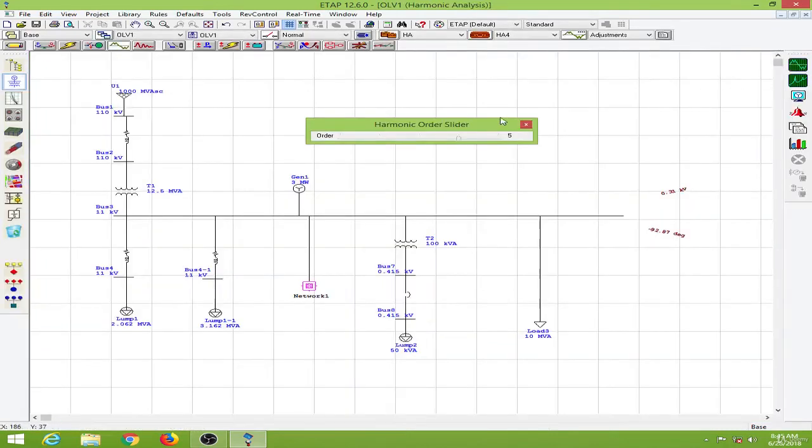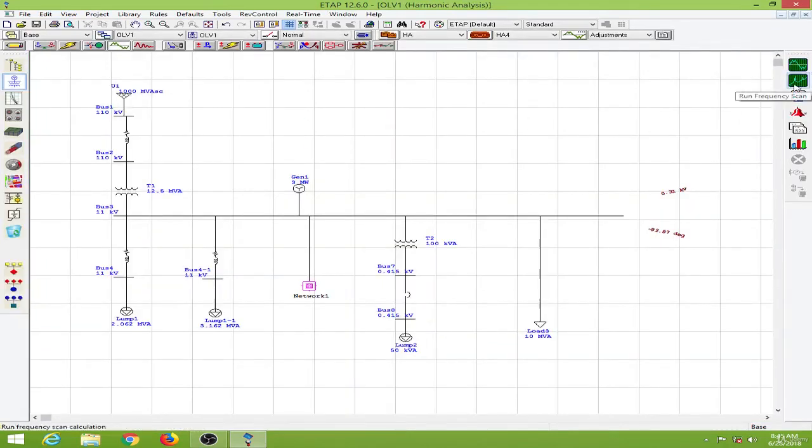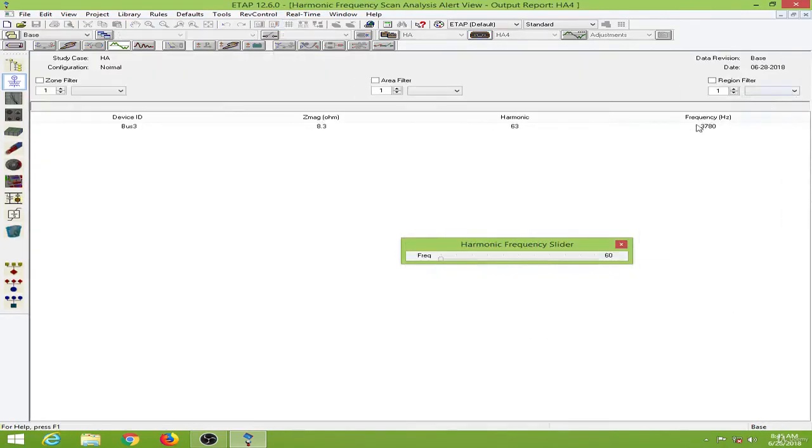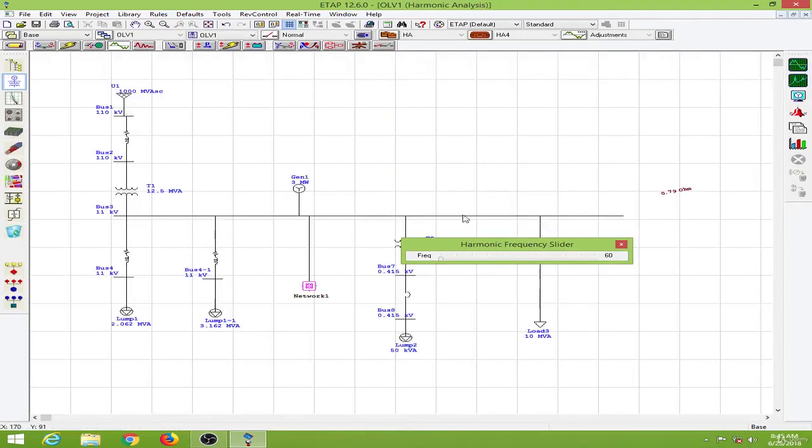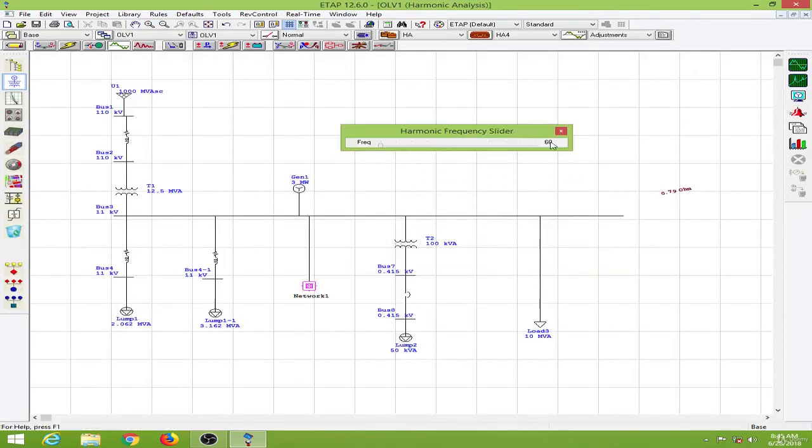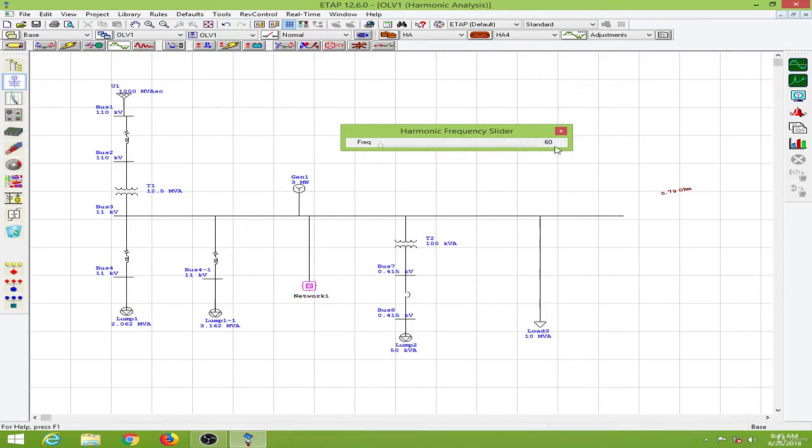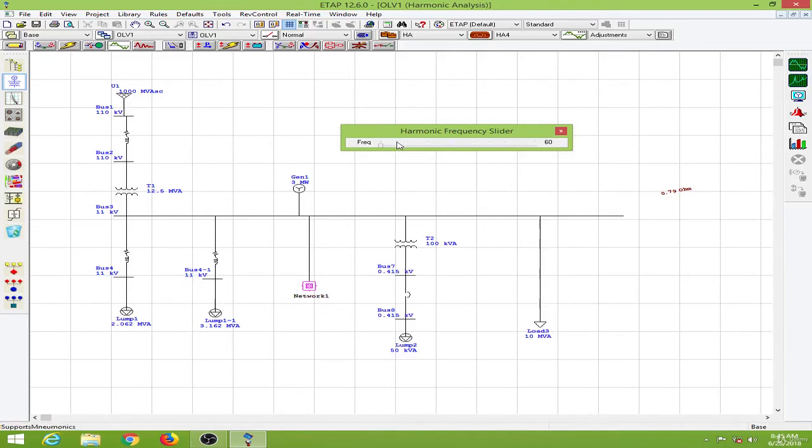And next I want to show you is the frequency scan. So running the frequency scan. Again we go to the alert window over here. Let me close this. So this system is operating at 60 Hz fundamental frequency. We have about 0.79 ohm, that is the impedance towards this frequency. Now if I change the frequency over here, you can see the impedance value changes accordingly.